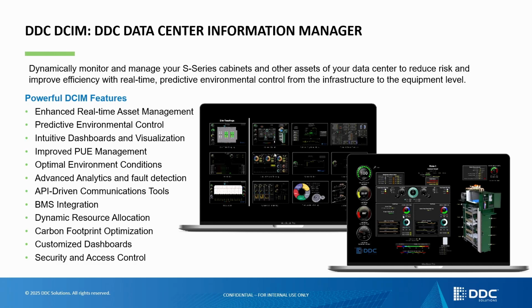By doing this in a very common and repeatable way, we end up reducing errors in the data center. We eliminate stranded assets because the software that manages the data center systems is all dynamic. That's truly what DDC stands for: dynamic density control. And if you're taking software and overlaying it on top of all this cabinet technology, using the vast array of sensors inside the cabinet to make data-driven decisions about how to allocate water to each cabinet, how to spin fans to guarantee CFM, all the different things that help drive efficiency up and cost down, all of that is integrated into the DDC system out of the box.